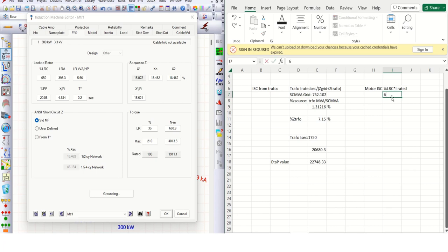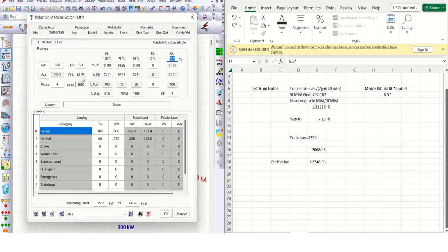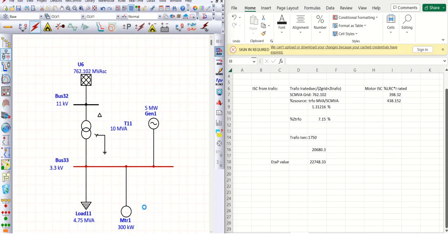It is 650%, that is 650 divided by 100, 6.5, multiplied by rated current. Go to nameplate, 61.28. You find the number 398.32. So this is the actual value, but ETAP always takes 1.1 times of this number. So it is 438 amps. Once again, while running, you may get this 438 number, 0.438 kiloamps.